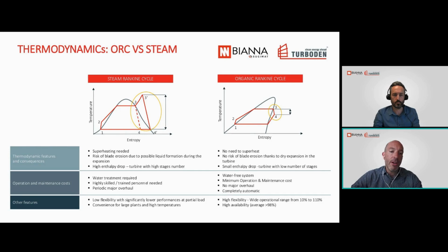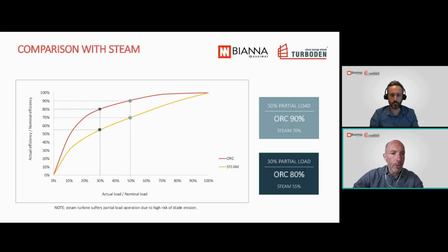Also, ORC are very flexible. They can automatically adjust power output based on changes in thermal input or ambient conditions. That makes the system really efficient. Maybe we can talk a little bit more about flexibility. If you take a look at the graph here, it compares how electrical efficiency behaves at partial load for both systems. What's interesting to notice is that when ORC is running at, say, 50% of the load, it still maintains about 90% of its nominal efficiency. Even when the input drops as low as 30%, efficiency stays around 80% of the nominal one.